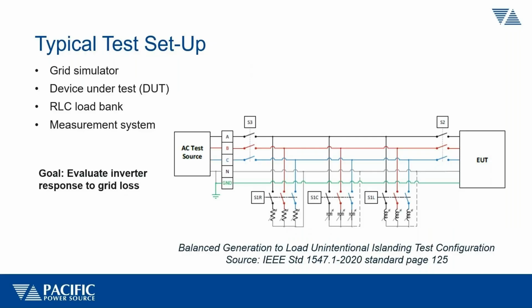Looking at the actual test itself, as I mentioned earlier, the test setup typically consists of an AC source that simulates the grid, or grid simulator. Because this is a DER test, energy has to be able to flow in both directions, so you need a regenerative source for this, typically. The EUT, in our case, is going to be a DER, like a PV inverter, that pushes energy back. In this test setup example, we're showing a three-phase DER, but it can be split phase or single phase as well, which simplifies test setup on single phase. This is a full three-phase setup, so it can handle any type of DER, depending, of course, on the power level of the grid simulator.